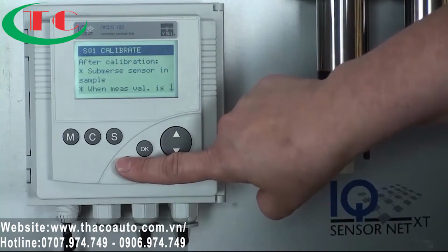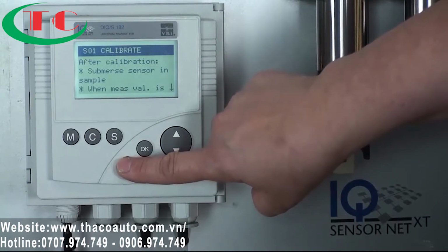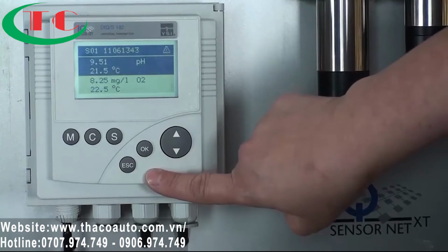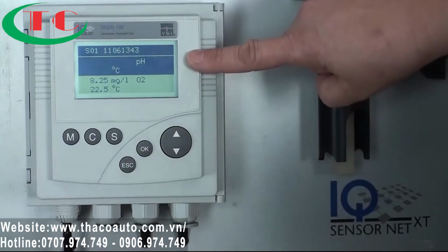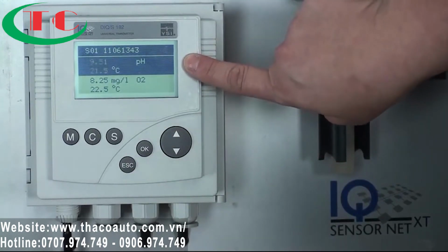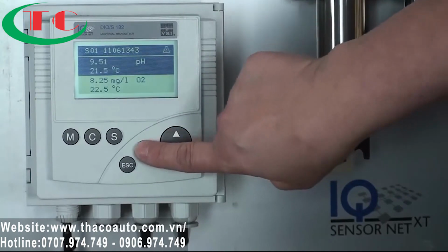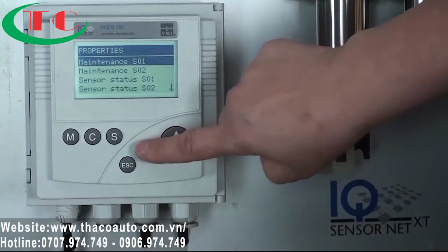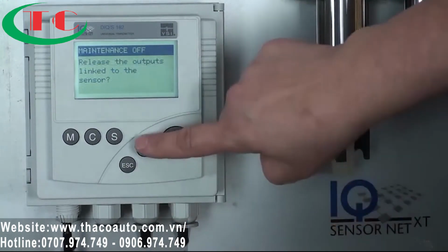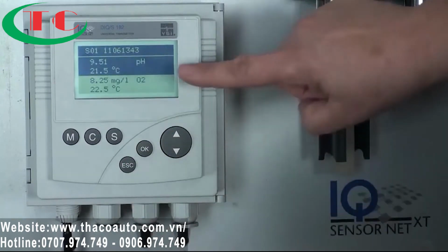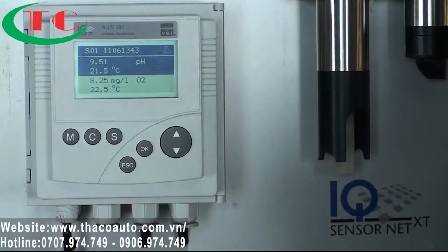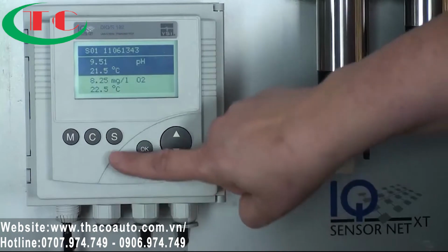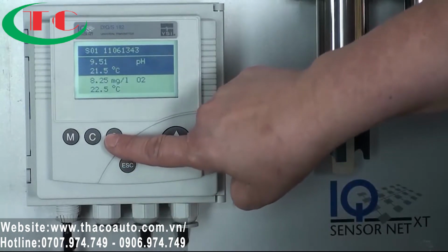I'm going to escape because I don't have any technical buffers ready and I don't want to block my sensor for measuring. Once again, we see that it is in maintenance condition, and as we did before, I'm going to press the OK button, sensor 1, release the outputs, OK, and as you can see, we're now out of maintenance condition. The last button we need to cover is the S button.